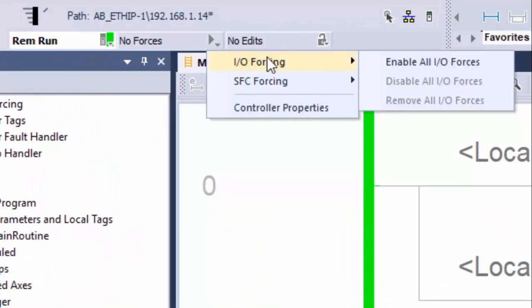From the force status menu, you can also use SFC programs. You must click enable forces for a force to take effect. You can only enable and disable forces at the controller level, and you can only enable IO forces and SFC forces separately or at the same time. Remember that you cannot enable or disable forces for a specific module, tag collection, or tag element.